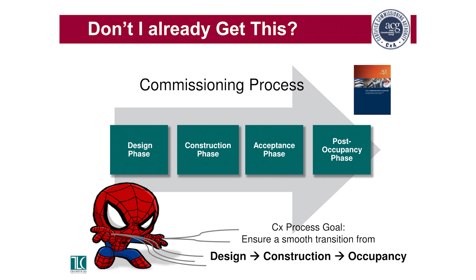Now that conversation has been helped a lot lately since IECC 2012 required some level of commissioning. At least people are more familiar with the term now than they had been in the past. But as you all know, code requires testing for HVAC in certain instances, lighting, and hot water now, but says nothing about emergency power systems. So it's important enough to test that HVAC systems work right, but we don't have to make sure emergency power systems work right in a hospital. I need to talk to some people about that.